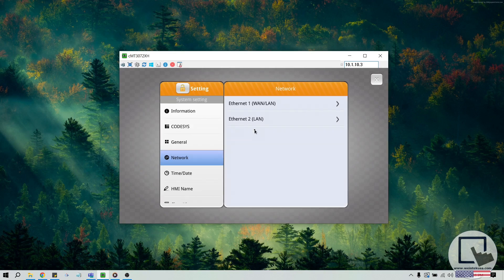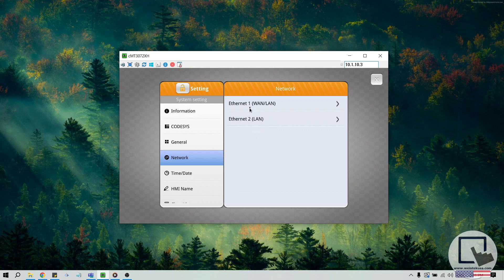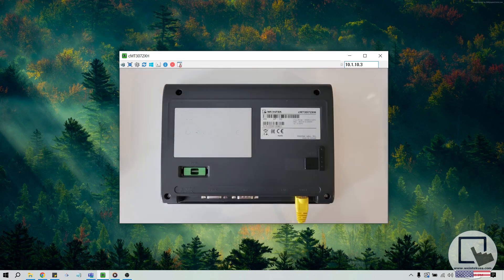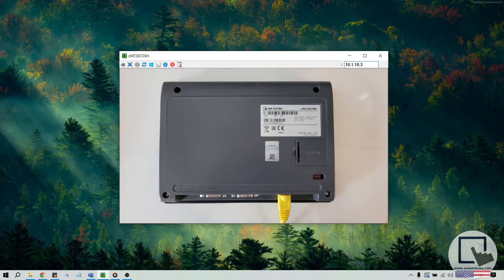At this point, if your HMI does not have a CODESYS license, please connect the HMI's LAN 1 port to an internet access point, like your router, then click Ethernet 1. If your HMI does have a CODESYS license, please connect the HMI's LAN 2 port to an internet access point, and click Ethernet LAN 2.